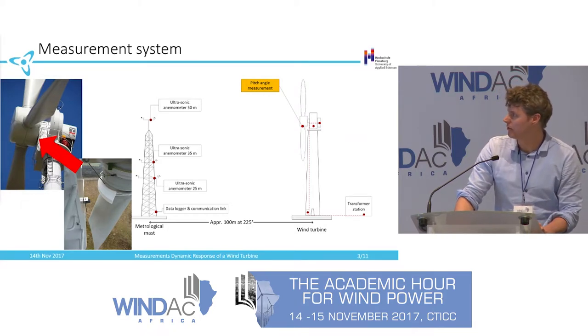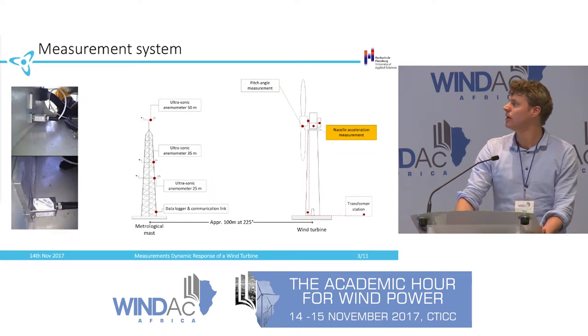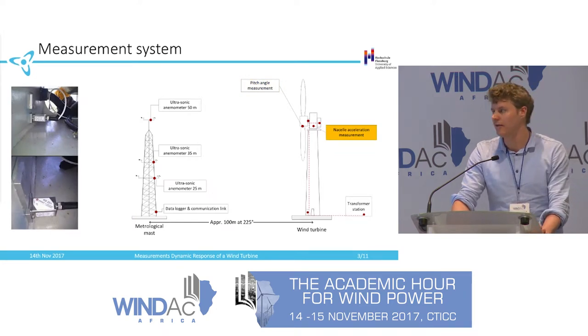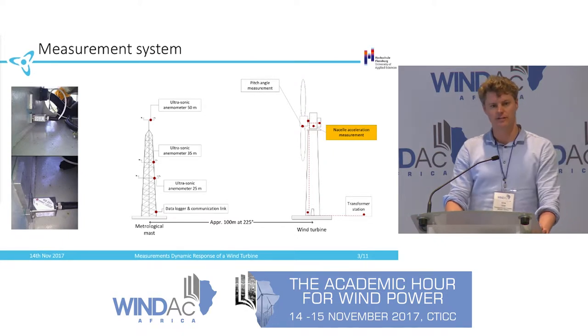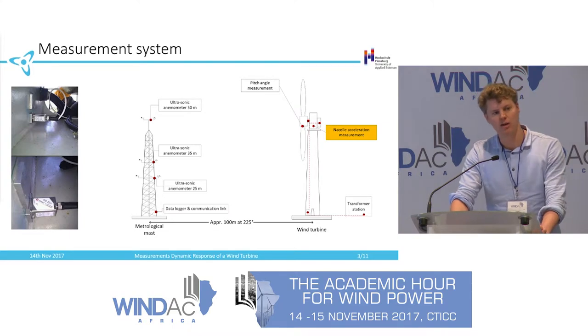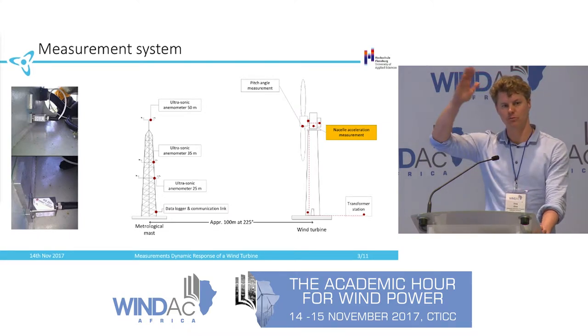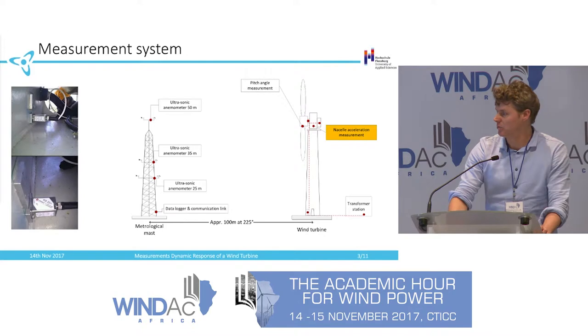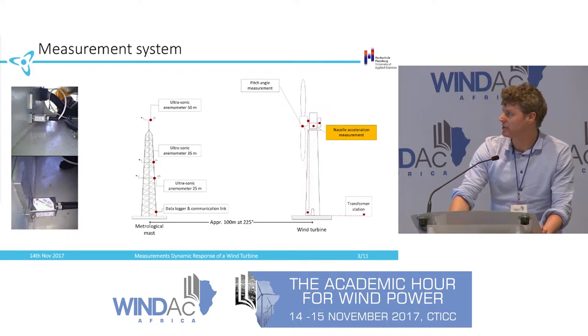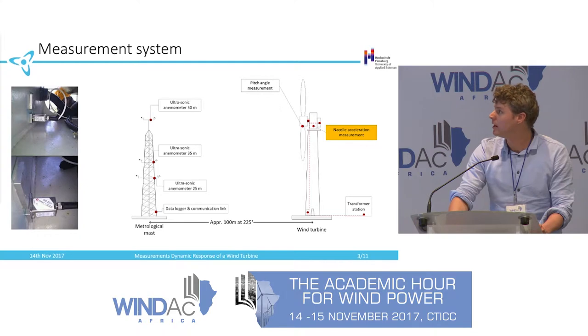And the next thing was, we have a lot of vibrations in the tower. So in some situations, we see that the turbine actually shuts down because the tower head moves too much. And in order to measure that situation, we have an acceleration sensor put in place up there as well.